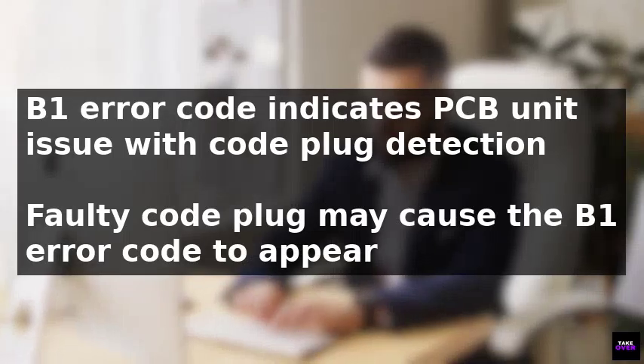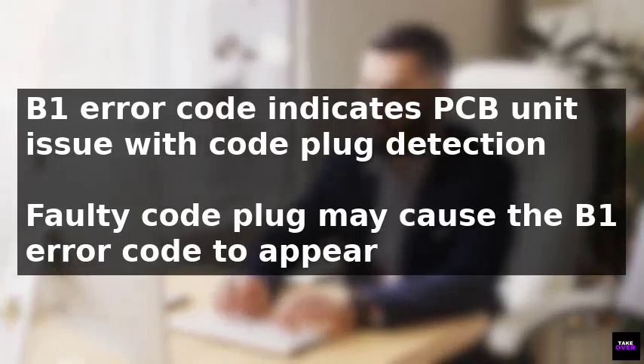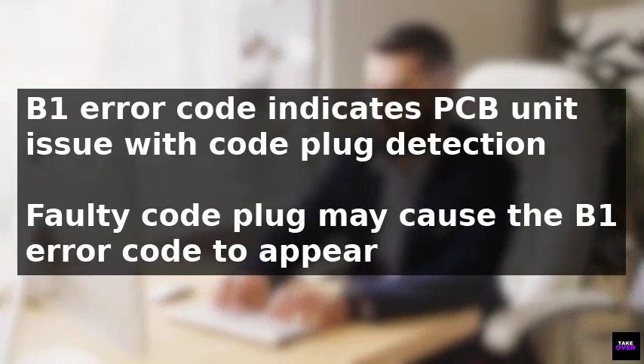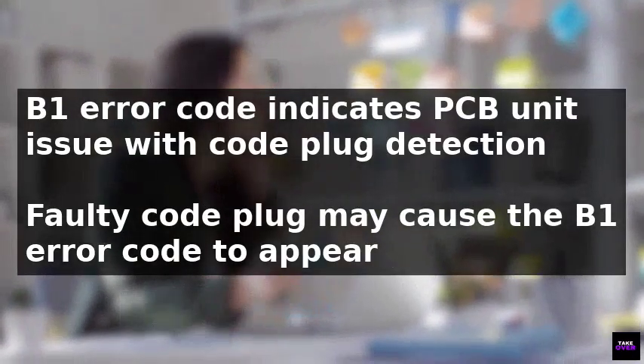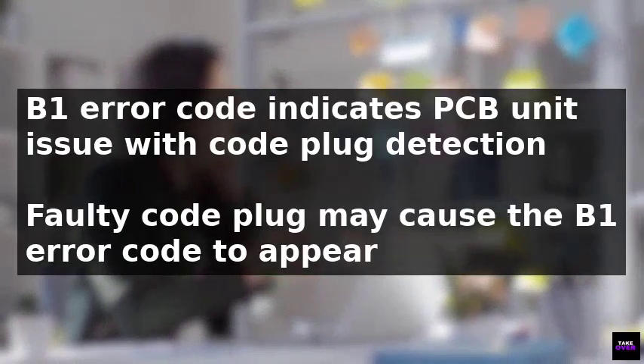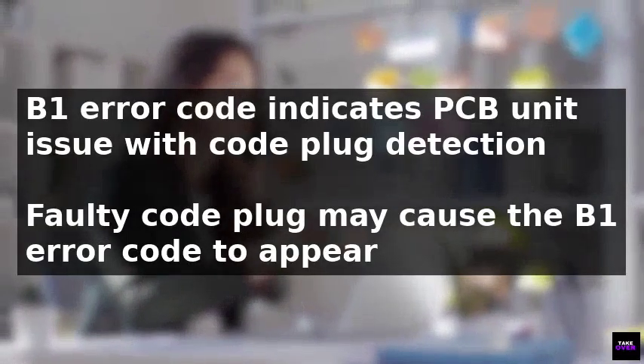The B1 error code on a Bosch boiler indicates that the appliance's PCB unit is unable to detect the code plug. This issue can be caused by a faulty code plug. To resolve the problem, several steps can be taken. First, resetting the boiler may fix the issue. The method of doing so depends on the model.